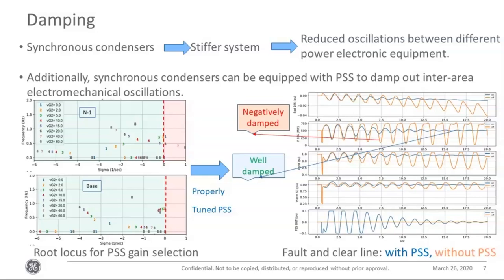the screen, but you can see that in the base case, there's a set of roots 1 through 8, and these poles of 1 through 8 are with increasing gains of the PSS that was equipped on the synchronous condenser. So you can see that in the base case, without any PSS, that is with a gain of 0, that's point number 1, there's this set of poles which is very, very close to the right half plane. So that's a very poorly or almost undamped oscillation without PSS.